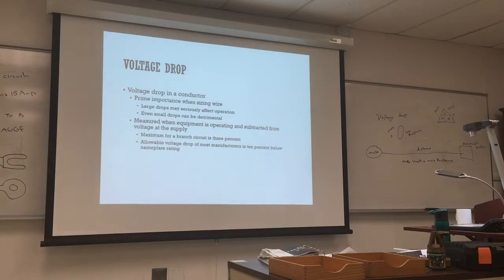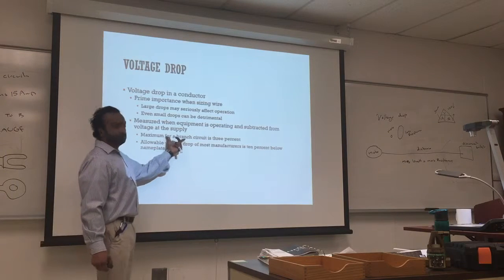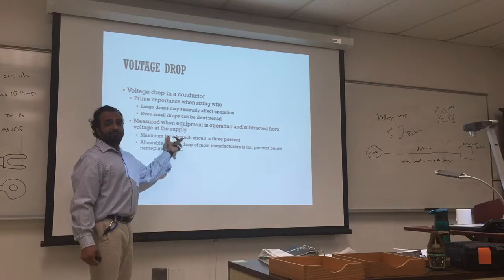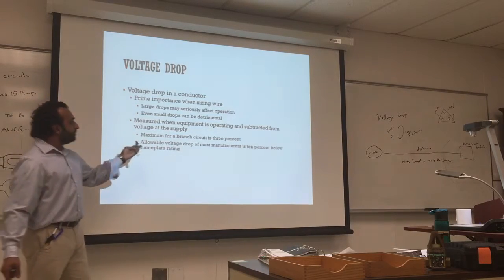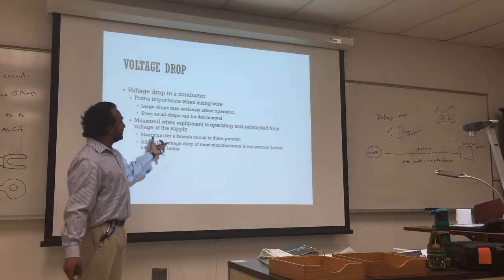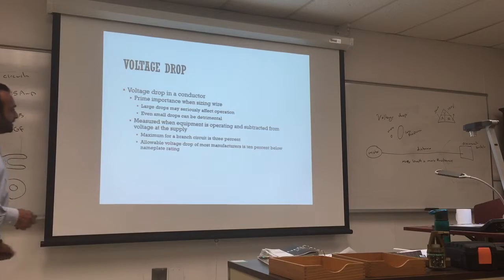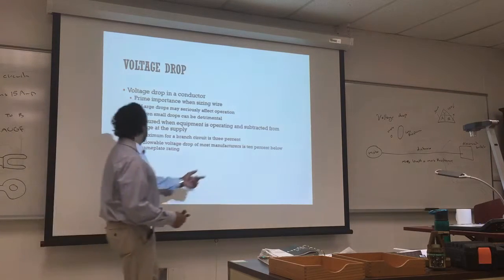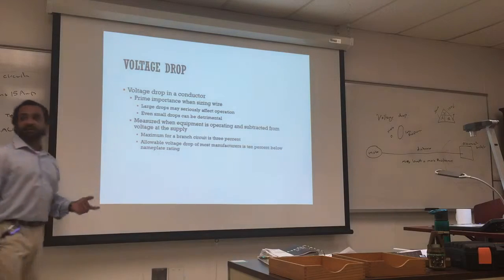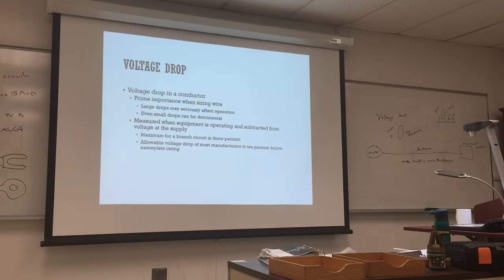There's a maximum for a branch of 3% voltage drop. If we have a branch from the main line, we want the drop to be 3% tops from the actual. There's an allowable voltage drop from most manufacturers of 10% below the nameplate rating - 10% for main equipment and 3% for a branch. What's the branch? If you take something in parallel from the main line, it should not be more than 3% drop. Remember the 10%, and don't forget about the branch - mostly 10% is the maximum drop.